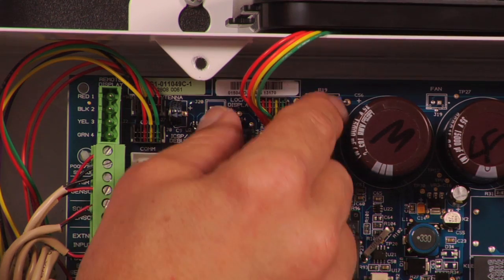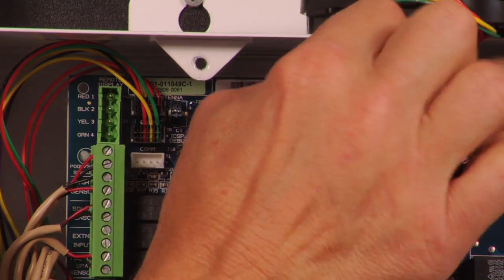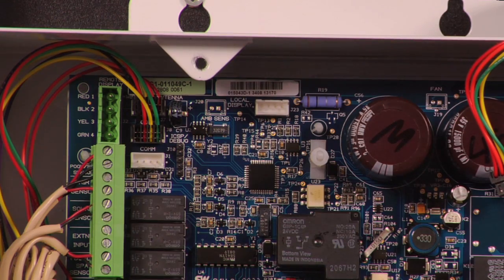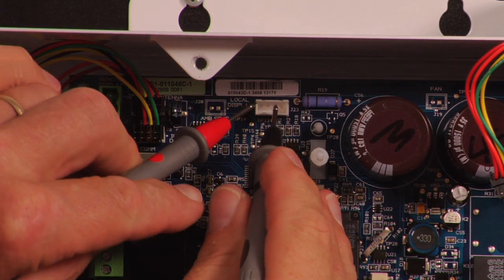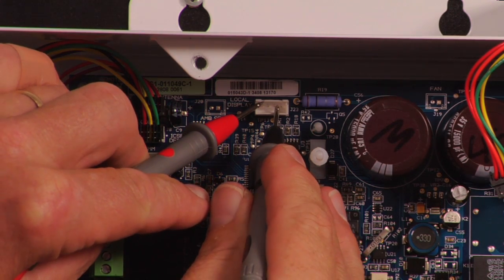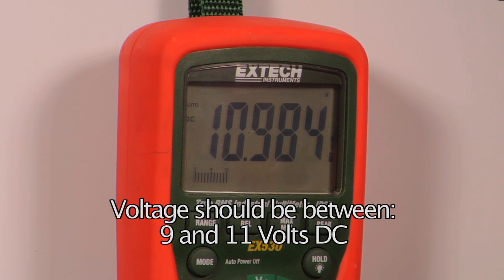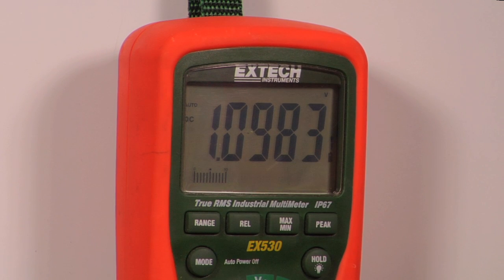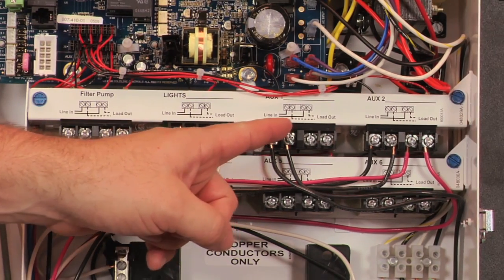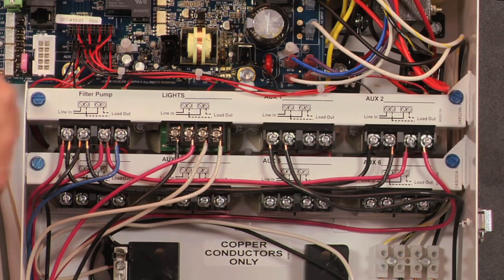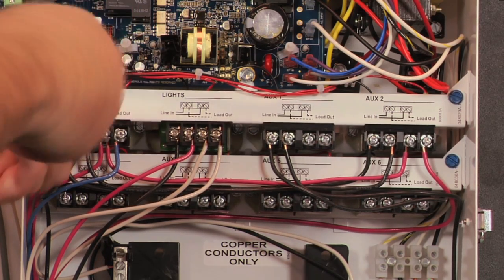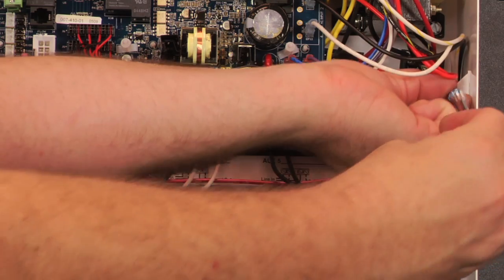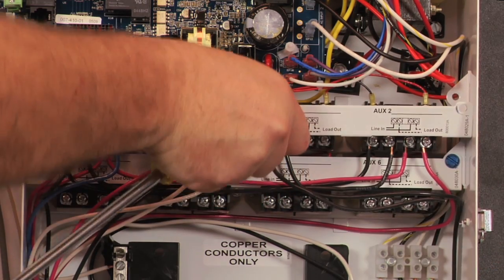If the voltage is good, unplug the local display connector from the main board. Measure the voltage between pins 1 and 3 on the connector on the main board. The reading should be 9 to 11 volts DC. If there is no voltage, replace the main board. If voltage is present, replace the local display. If a piece of equipment connected to one of the high voltage relays does not turn on when the corresponding button is pushed, there may be a problem with the ProLogic main board or the high voltage relay.